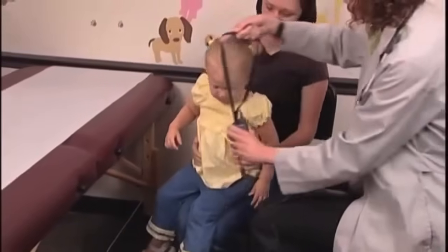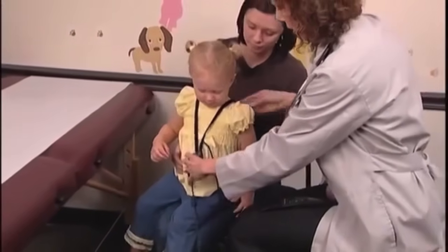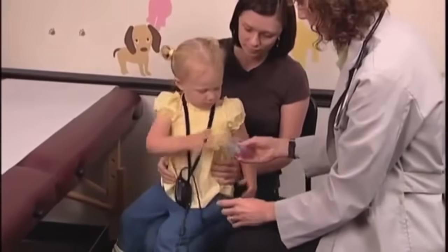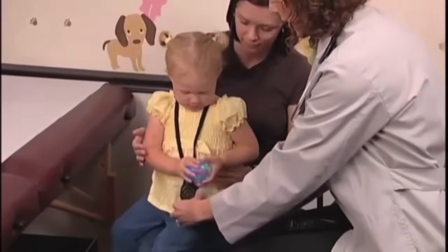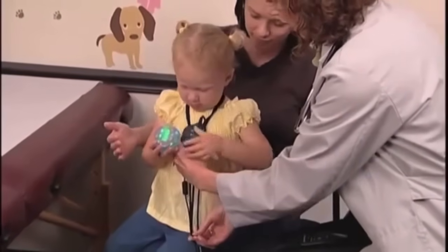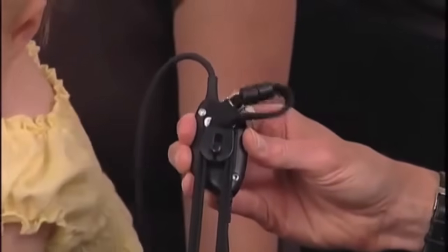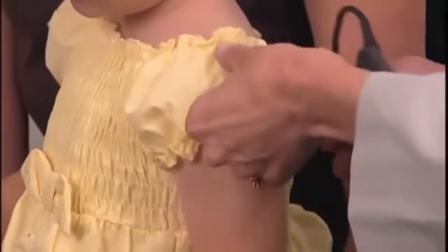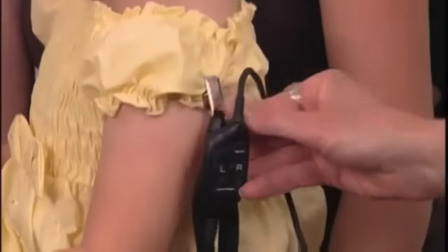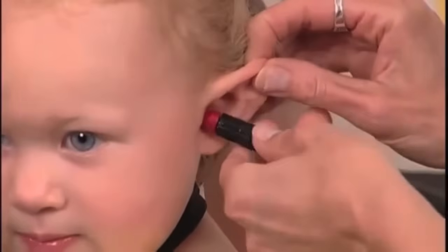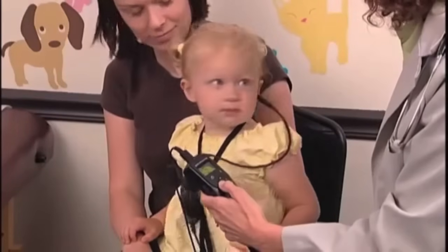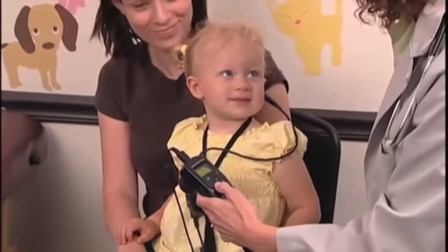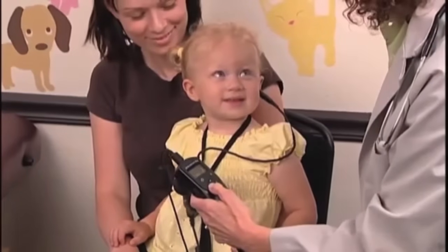First, as we just mentioned, eliminate as much noise as possible in the testing area. Then, make the patient comfortable by having them sit or lay down. Once they're settled, secure the external probe to the patient either by using the attached lanyard as a neck loop or by cinching the loop up and then using the shirt clip to attach it to the patient's collar or other article of clothing. The probe enclosure should be placed close enough to the patient's ear so that the probe cable has room to flex and cannot pull on the probe. Insert the probe into the patient's ear.